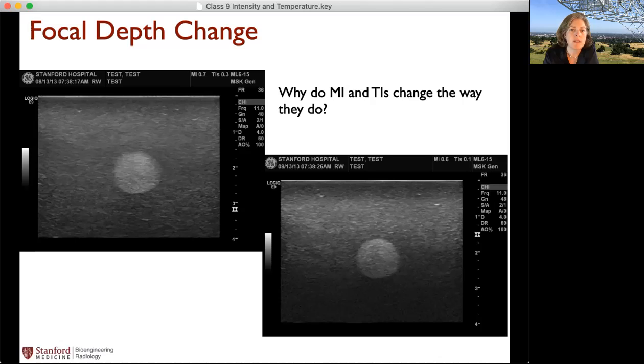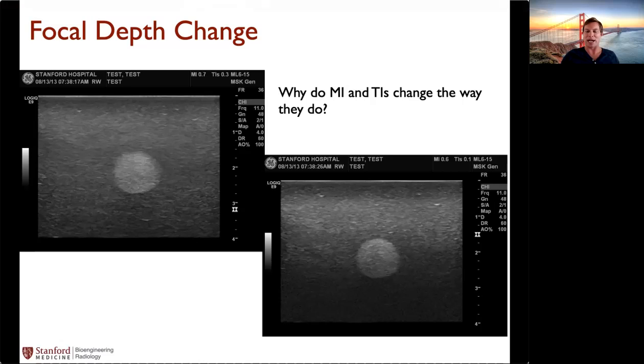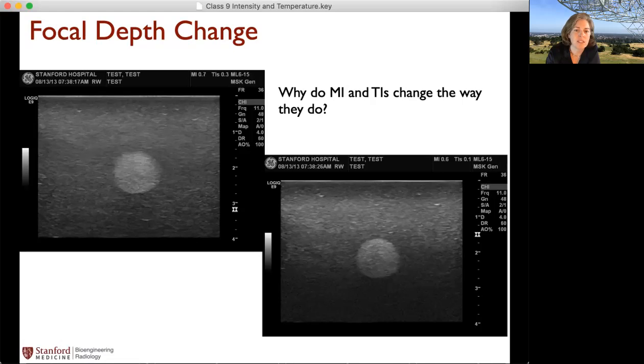The frequency is the same. We're using harmonic imaging and everything else is the same. Any ideas, Keith, for why it's a lower TI in the second image than it is for the first image? Oh, yeah. So I would guess that they're just using more power to get more reflection intensity at the depth that they need. That's my guess too. More power is needed to get to that depth.